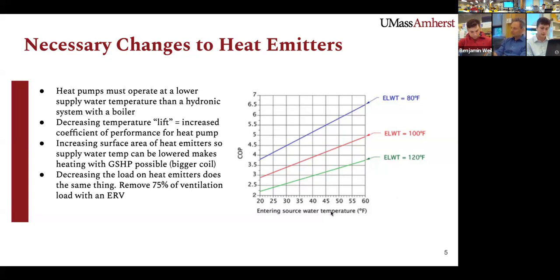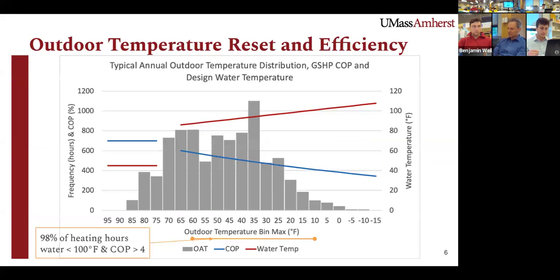On the x-axis, the entering source water temperature is the temperature of the water that is received from the ground, which is typically around 50 degrees. Looking at the green line, for example, when the system's water is at 120 degrees, the efficiency of the system is just below 350%, or a coefficient of performance of just below 3.5. Whereas if we are at a preferred range of 80 degrees to 105 degrees, which the proposed system will allow for, the efficiency will range from 450% to just below 600%, which is a drastic increase. This will be achieved by increasing the surface area of heat emitters so the temperature of the supply water can be lowered, and also by decreasing the load on heat emitters.